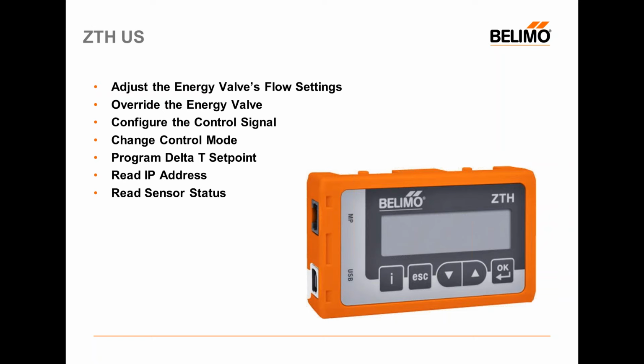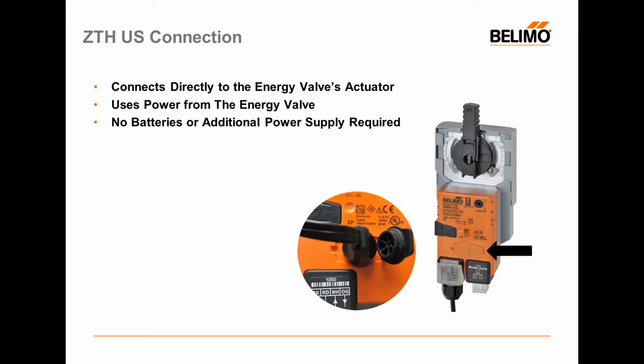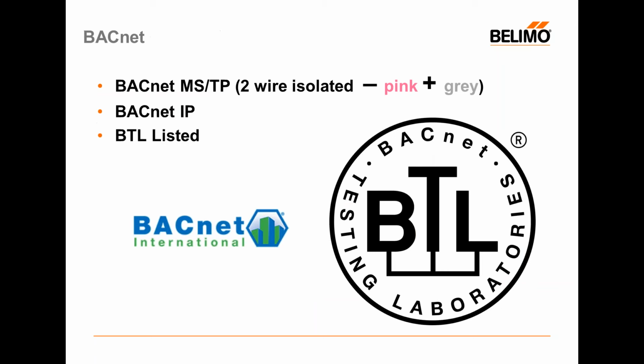So if you do not know the IP address of your existing energy valve and you plug in the ZTH-US, it will find the IP address for you. So at the very least, you can rediscover your IP address with the ZTH-US, a great tool just as a safety if you're networking your valves and somewhere along the line a couple IP addresses get misplaced. As I said, we connect directly to the face of the energy valve. So you can see here we have the small connection point. You open the cover, simply put the connector into the energy valve's actuator. It'll power up the ZTH-US and discover it and provide you all the information and the ability to make the changes you'd like to make.